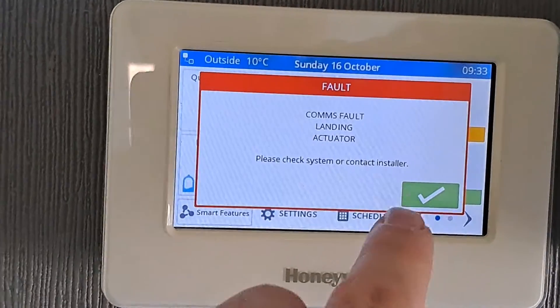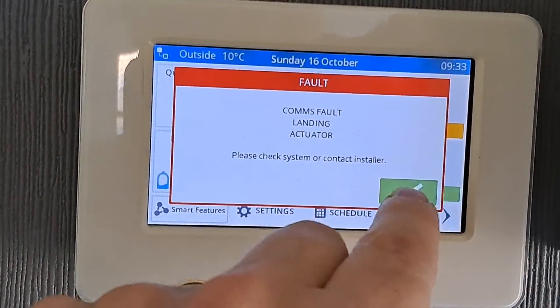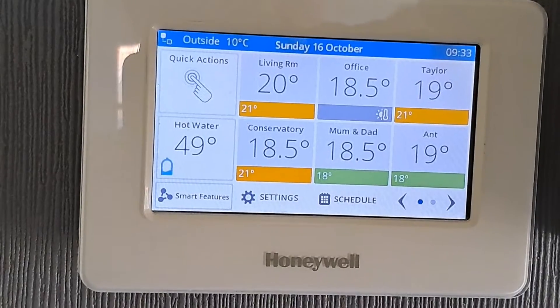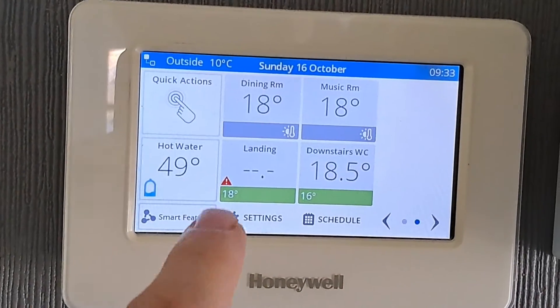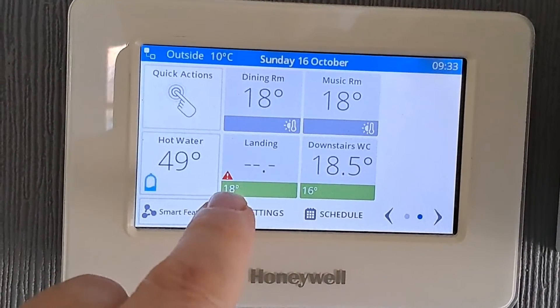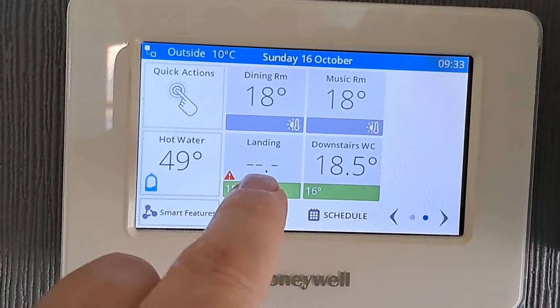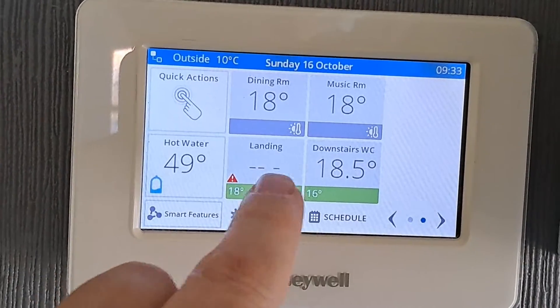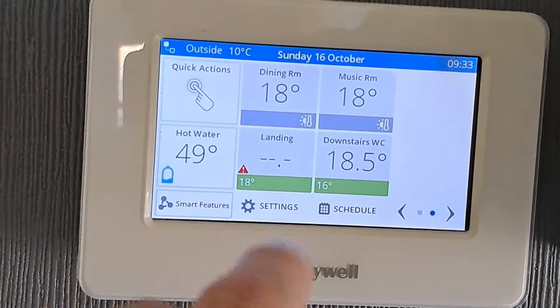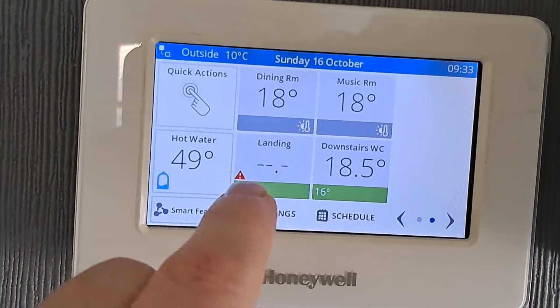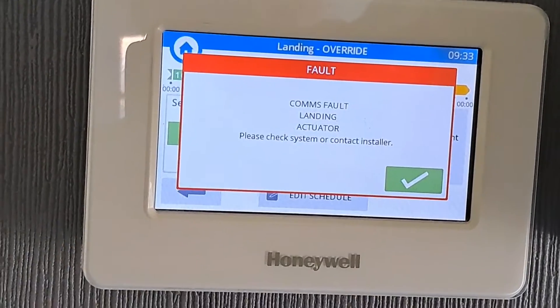It just means there's no control over that zone at the moment. I'll press the tick, and if we look at the zone we can see a little warning triangle symbol and no temperature is being displayed, so it's a fair bet that that particular valve is currently offline. You just press on it...